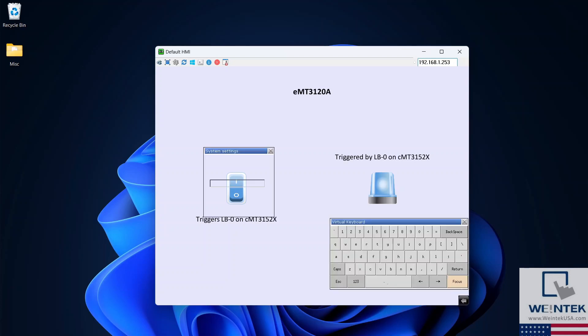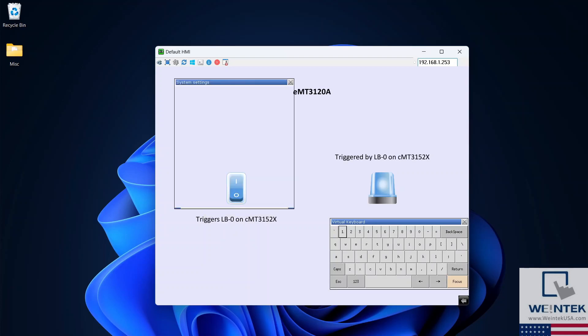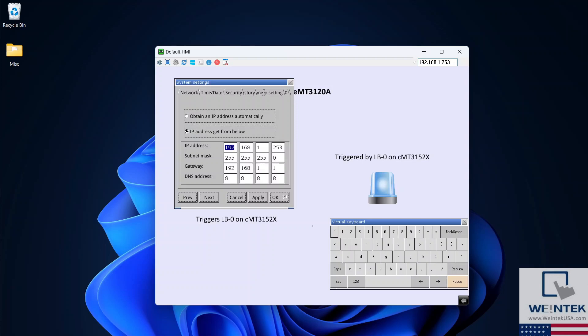You will be prompted to enter the HMI's password. 111111 is the default password for all Weintek HMIs. In the network tab, you can statically assign network info like I have, or you can obtain an IP address automatically via DHCP server.